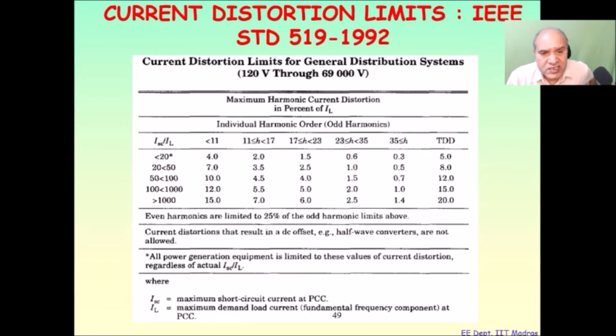We will analyze some of the standards here and see how they are being interpreted or considered for the power system. For example, if we say IEEE 519, then it says that based on the voltage level of the distribution system, these are the permitted harmonics levels in the system. For example, for 120 volt to 69 kilovolt, the permitted harmonics are given in this table. So there are two parameters. First is the voltage level. Second is the ISC by IL. What is ISC by IL? This is the ratio of short circuit current to rated current or load current.